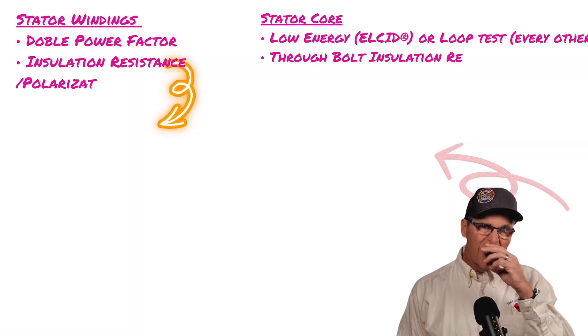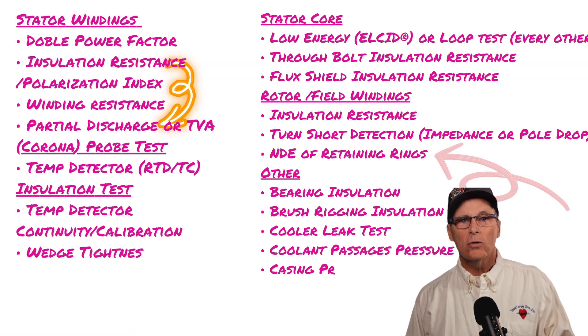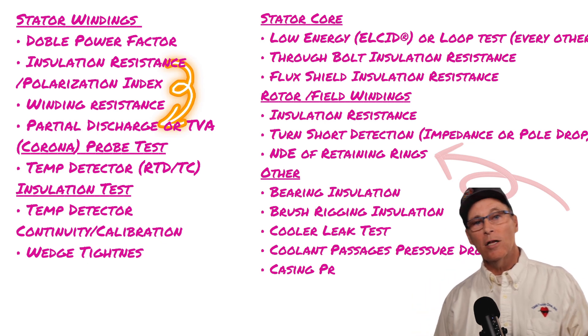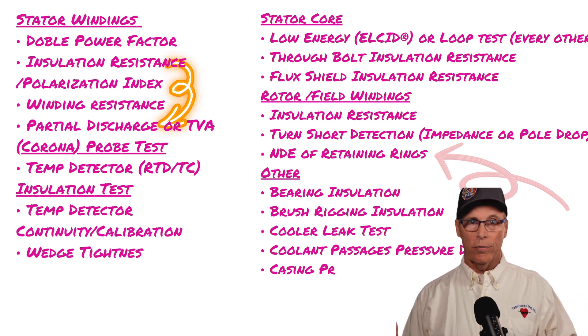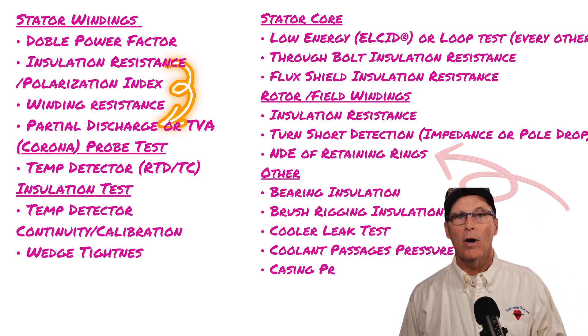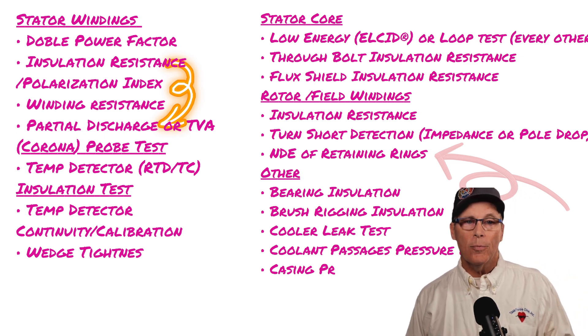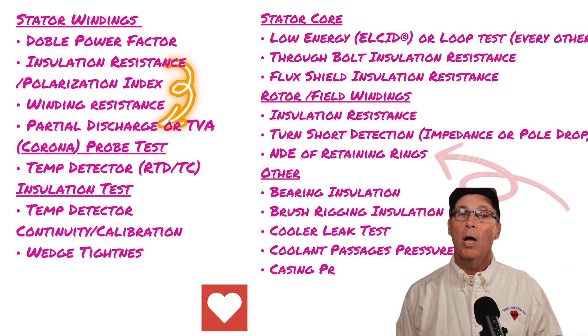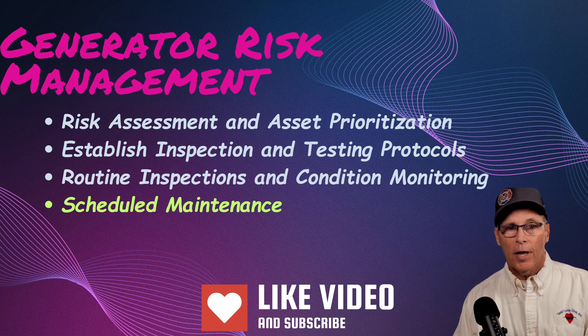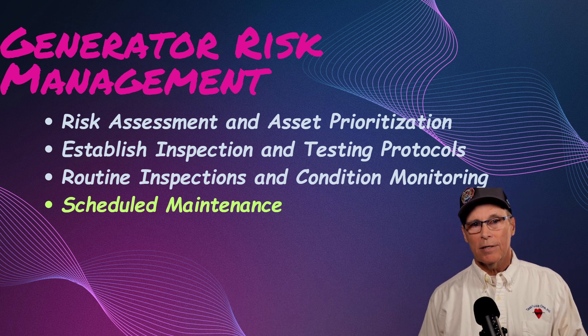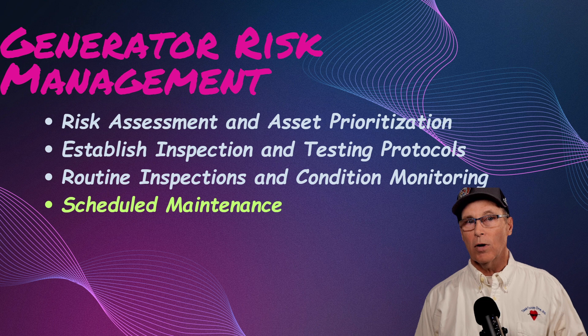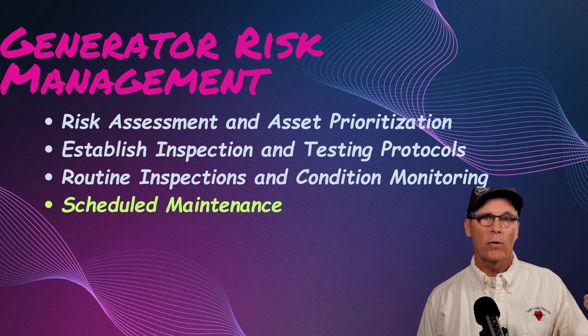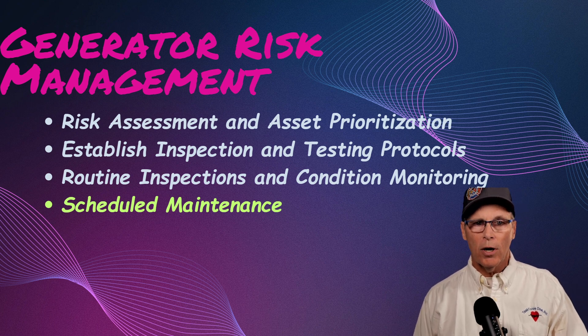These are things you'll want to do to maintain and inspect your machine. NDE of the retaining rings is really important — once you do it, you'll know if you have the good ones or the bad ones, so you don't have to keep repeating it. Partial discharge monitoring is sometimes recommended by insurance companies to improve reliability. For scheduled maintenance, we're not just looking — we're actually taking things apart and cleaning them, because drawing in cooling air brings in dust and moisture that builds up.